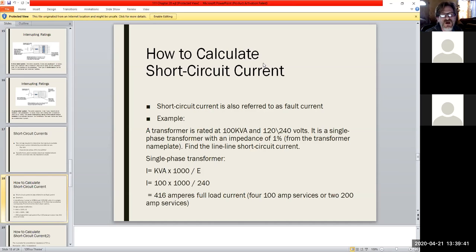So with that in mind, basically, your transformer is rated at 100 kVA at the 120/240, right? So you have an impedance like 1%, which is pretty low. I mean, it's very, very minimal. And so to find what your short circuit current would be, you basically would set your I, which stands for current, equal to your kVA multiplied by 1,000, divided by the voltage. In this case, our maximum rating is 240 volts, usually going into the home because you have the two lines. But still remember, this is only a single phase system, but that's what you would use.